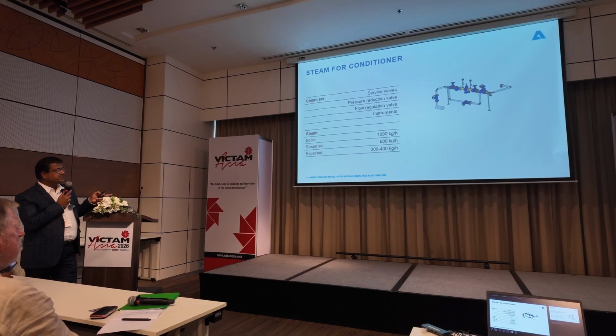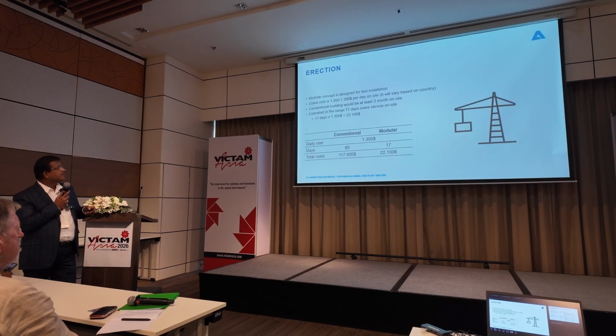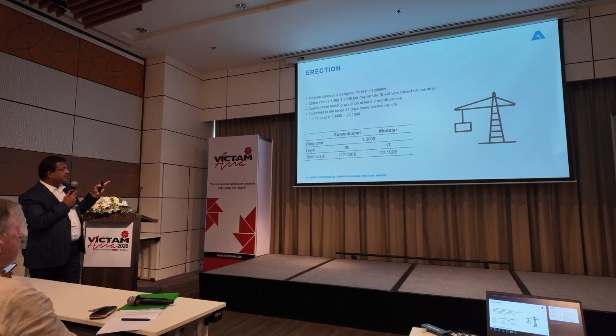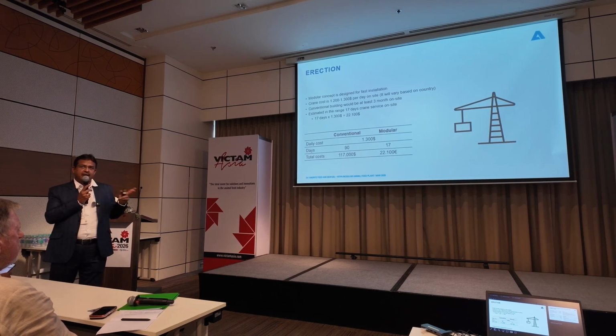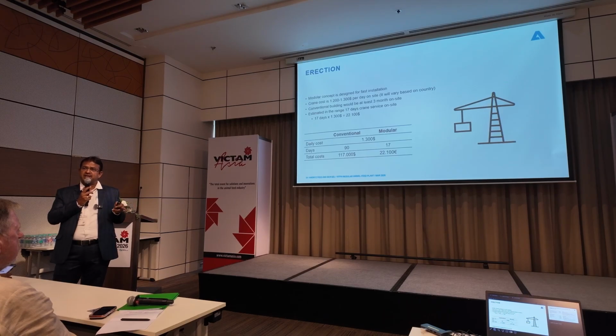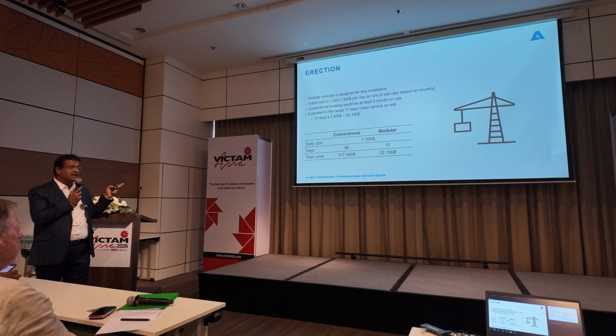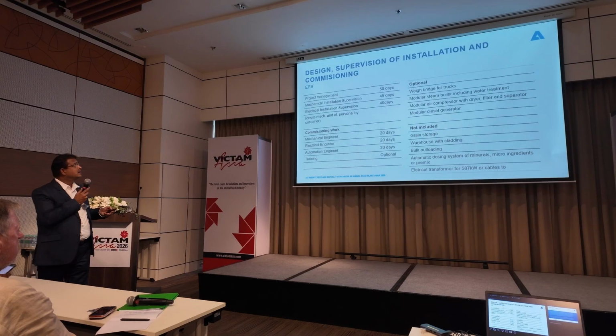And the steam for the conditioner, a 1 ton boiler, is required from the customer side, and all the PRS station is included in our scope. Erection was initially fixed at 90 days, but we were able to complete it within 60 days due to an urgent requirement for Kargil. That's how we came up with 2 months to install.